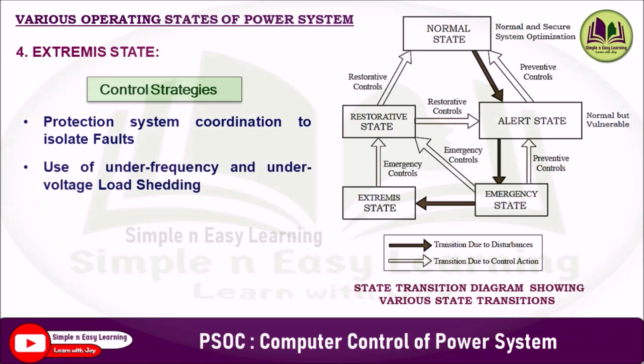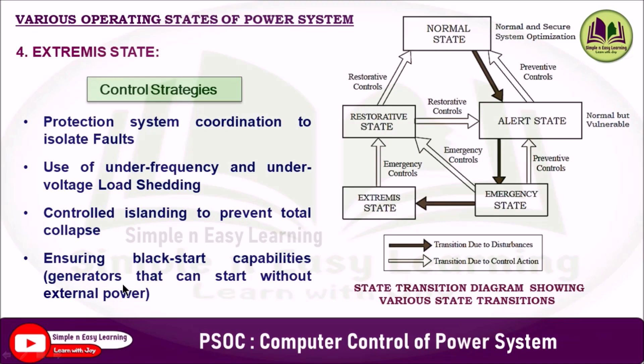Control strategies in the extremis state include protection system coordination to isolate faults, use of under-frequency and under-voltage load shedding, controlled islanding to prevent total collapse, and ensuring black start capabilities. Black start is the process of restoring a power system to operational condition after a total or partial blackout without relying on the external transmission network. Causes of blackout include natural disasters, equipment failure, cascading trips, cyber attacks, or grid instability. Since most power plants require external grid power to start, special black start units must be used.